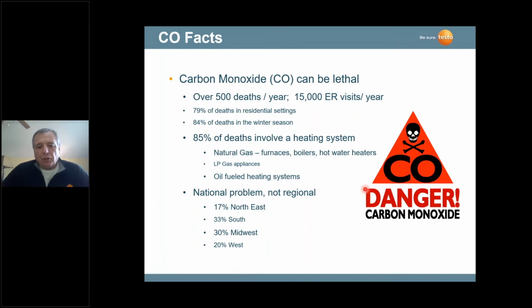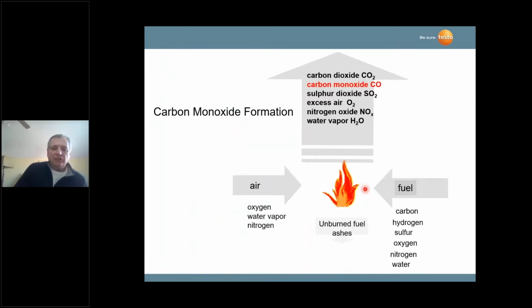We have such a short heating season, and a lot of the service technicians and contractors don't use carbon monoxide measurement when they're looking at furnaces and boilers. Commercial guys do, but on the residential side, we're not doing very much combustion testing. As a result, we have a very high percentage of fatalities in the United States per year. Keep in mind that carbon monoxide is a formation of too much fuel, not enough air, and it's CO. Again, CO2 is a totally different type of gas.